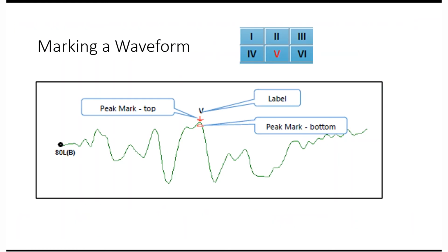When you mark a waveform, you're going to highlight that waveform. So any waveform in green is the active waveform. And right above 80 dB there on the left of the waveform, you can see a black circle. That's what we call the waveform handle, if you will. You can click in that handle and move the waveform up and down or around or activate that waveform. So if it's green, what you would do to mark a waveform is select the marker that you want. In this case, if you look at my waveform markers, wave 5 is selected in red, and then you hover just above or just below the peak and left click and the marker will appear.